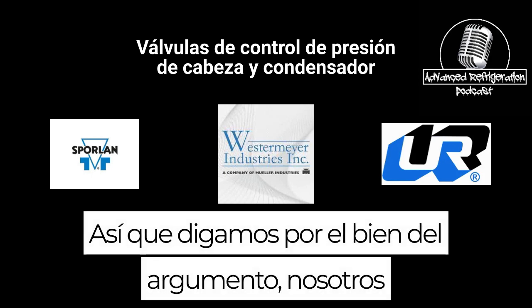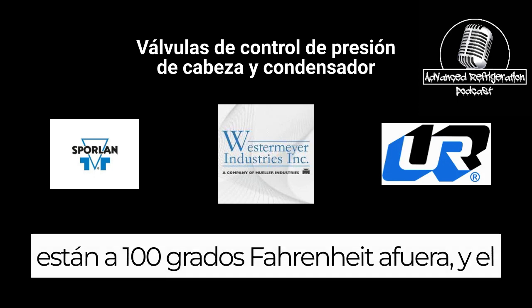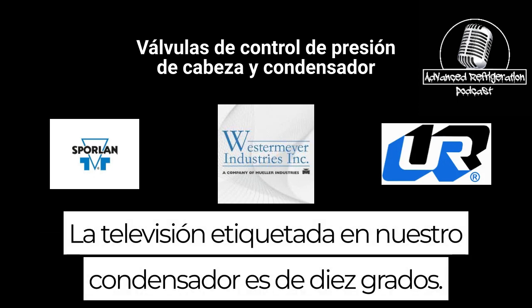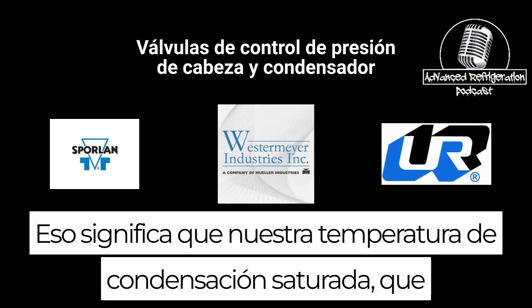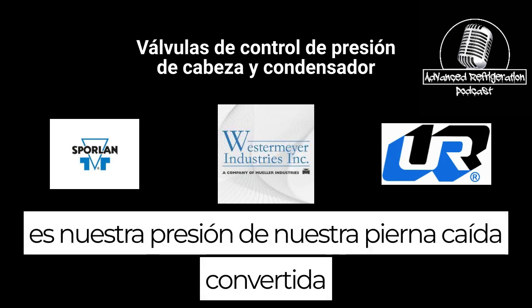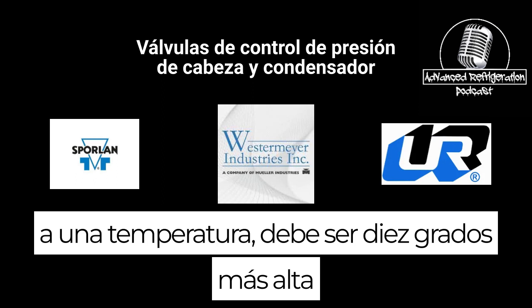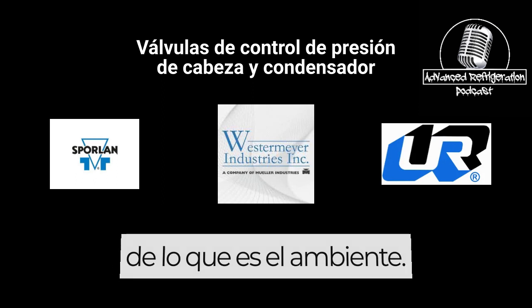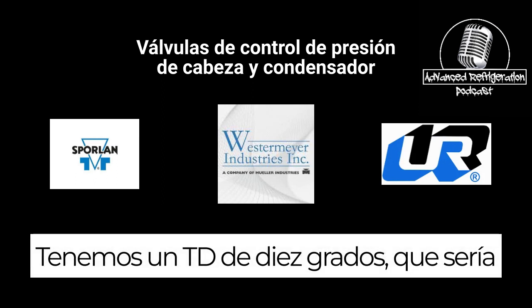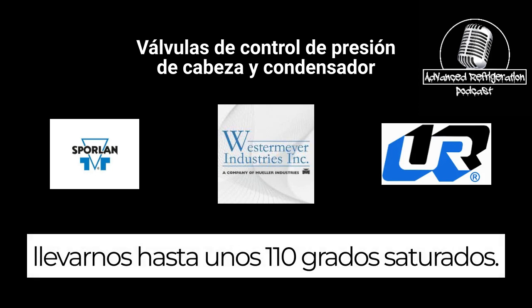So let's just say for argument's sake, we are at 100 degrees Fahrenheit outside and the TD labeled on our condenser is 10 degrees. That means that our saturated condensing temperature, which is the pressure of our drop leg converted to a temperature, should be 10 degrees higher than the ambient. We have a 10 degree TD, which would bring us up to about 110 degrees saturated.